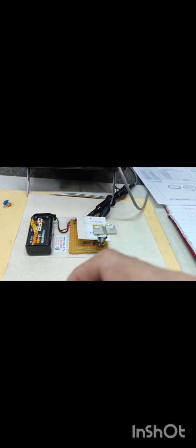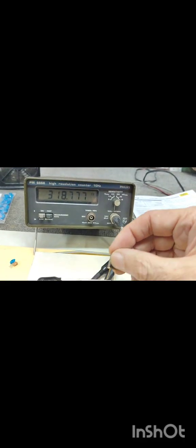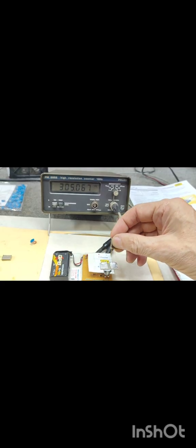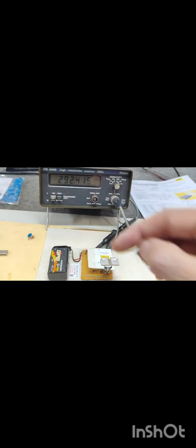So I can speed up and, from a batch of crystals, measure several hundred within a few minutes. The moment I touch, it gives me an instantaneous reading, and the moment I remove it, it's gone, which is extremely good.